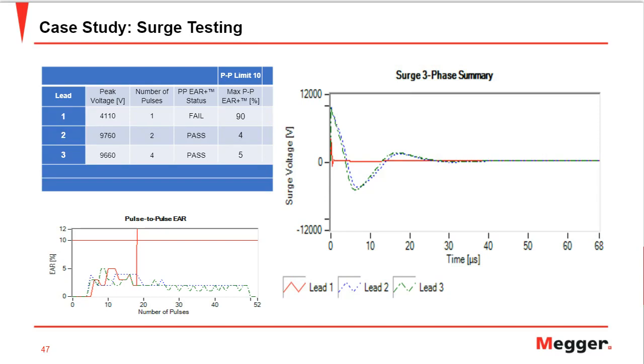But it's another good case study to help us see why surge testing and DC hipot testing are as important, or give you much more results on the predictive side of the maintenance program. Of course, the motor was sent back, checked, and it was up. This was a case done a few years back, and the company saved a good amount of money on unscheduled downtime. They were able to determine the insulation level of that motor before the motor went to the failure zone. And of course it saves the company a good amount of money, and most of all unscheduled downtime.